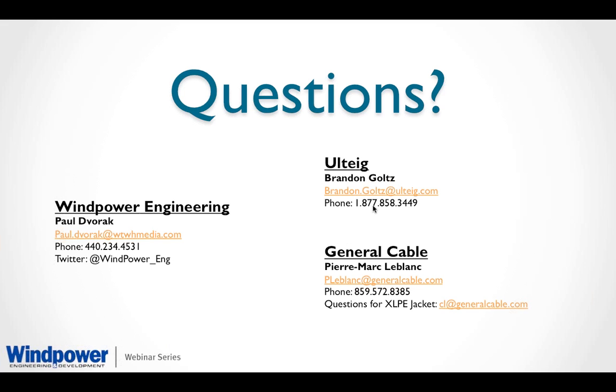Okay, one more question for you, Brandon. How do you come up with an optimized cable sizing scheme? Well, there are 2 ways that we've been able to do this. In both ways you have to build a model. Typically we use an electronic software program designed to model the cables and energy loss. You can run your scenarios and increase the size of the cables that have a larger loss on them. This is typically the heavier loaded cables, the ones that have more turbines on them, or longer runs. Another way we've done it is you take an average cable length and adjust the power through it.